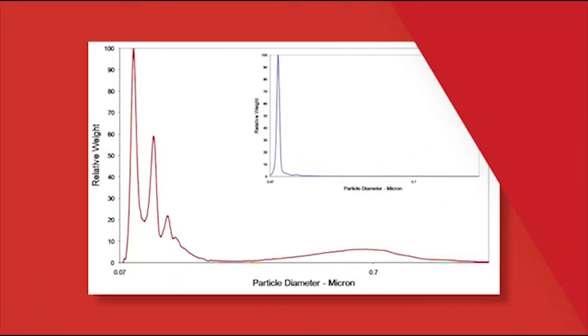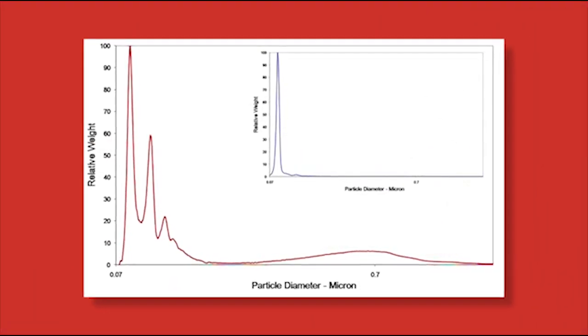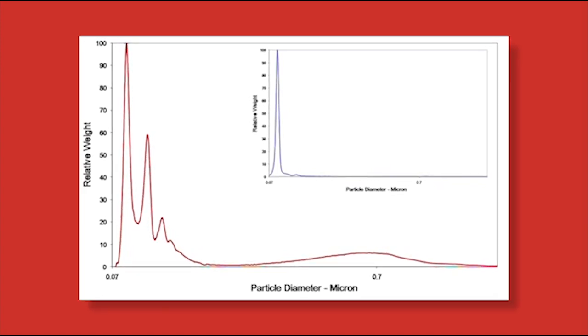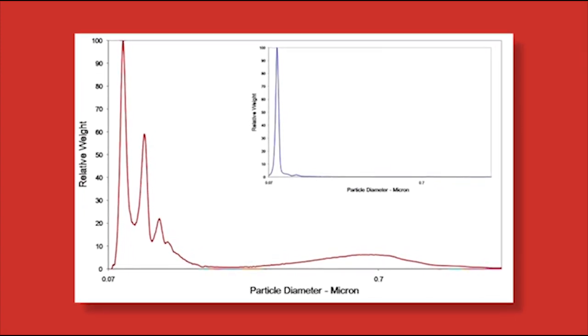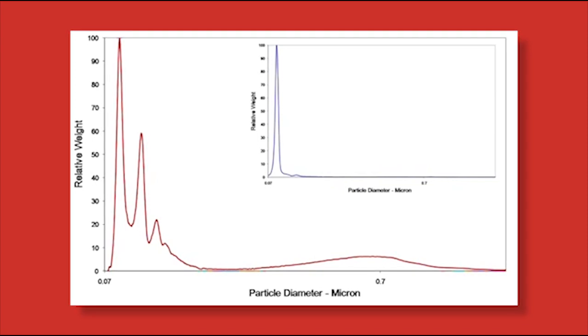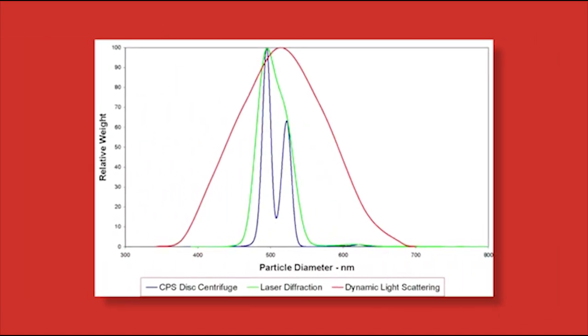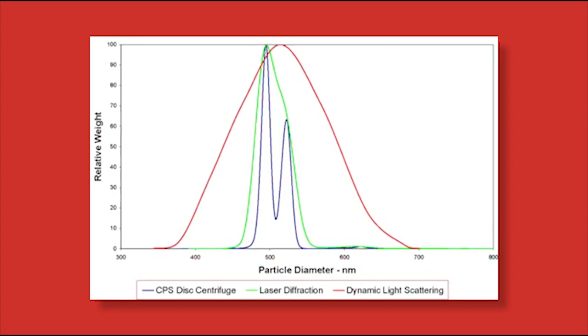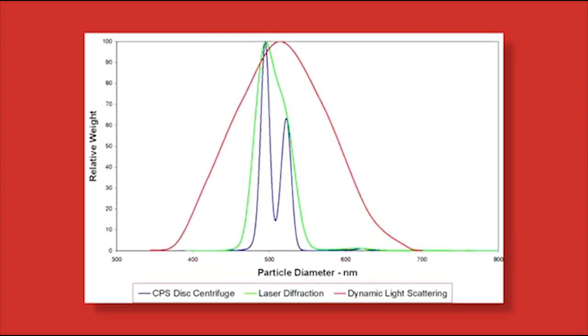We can actually show all of that with the CPS instrument and as we purify the adenovirus sample we can remove these agglomerates and show the clean pure peak. Most techniques you will actually struggle with the resolution and will be unable to see these agglomerates and aggregates in the sample.